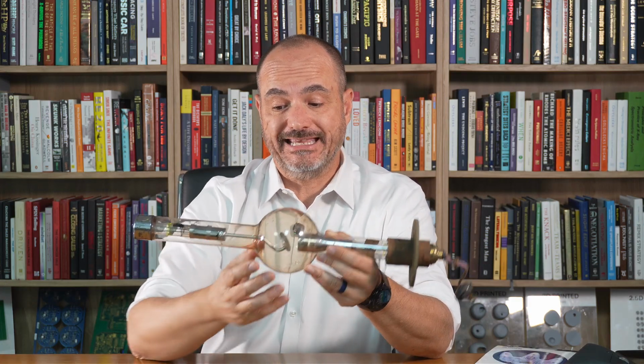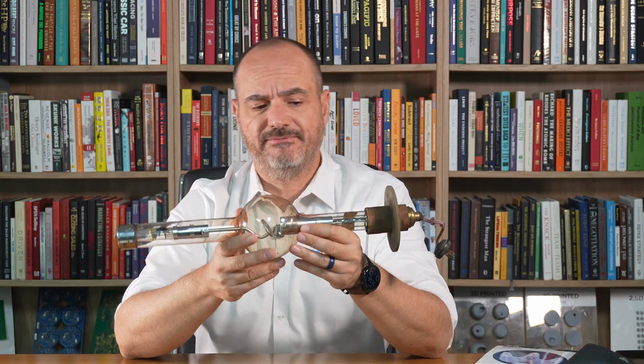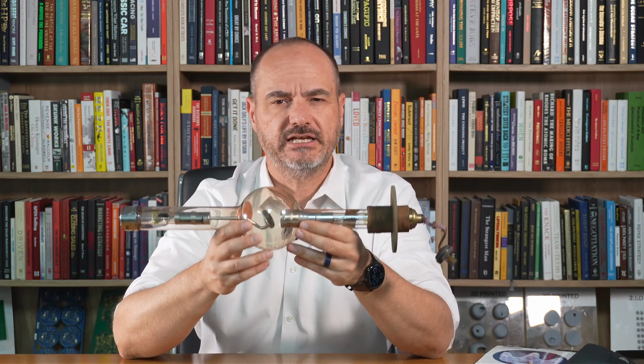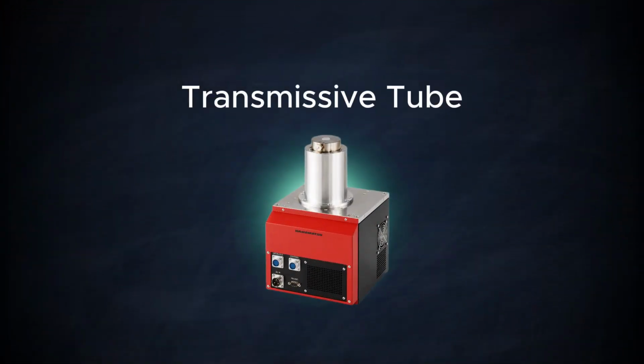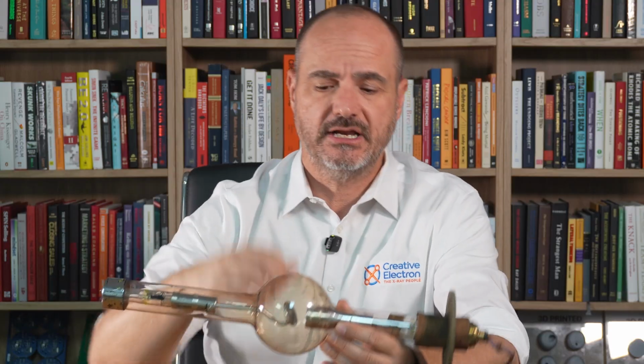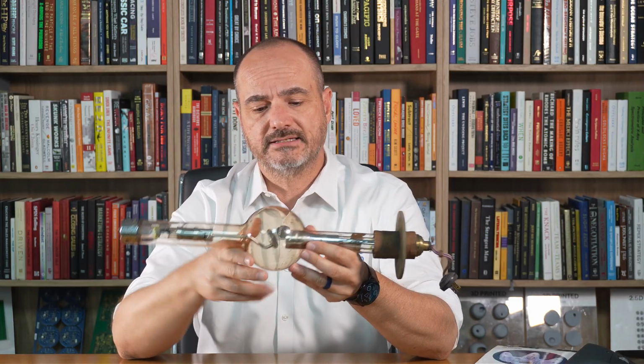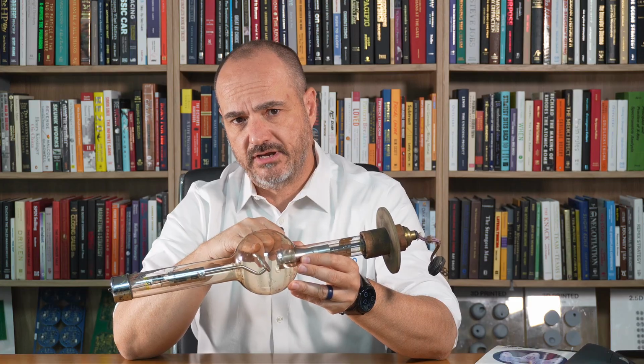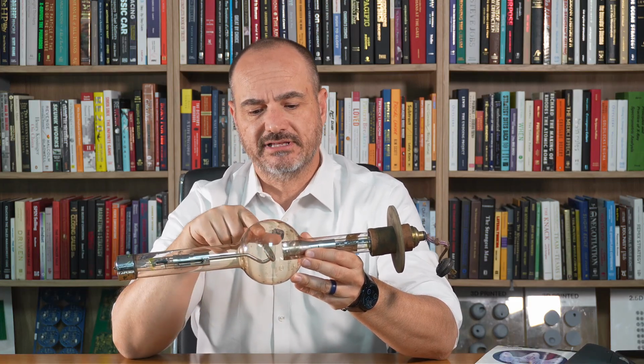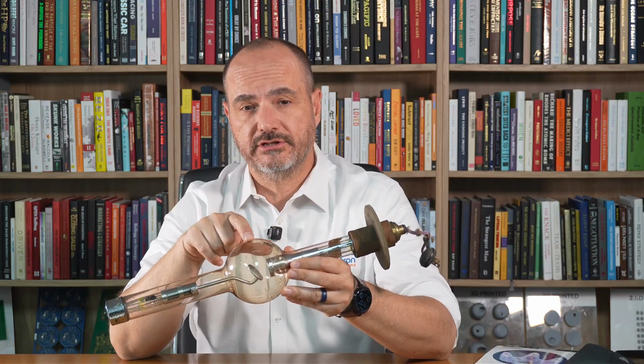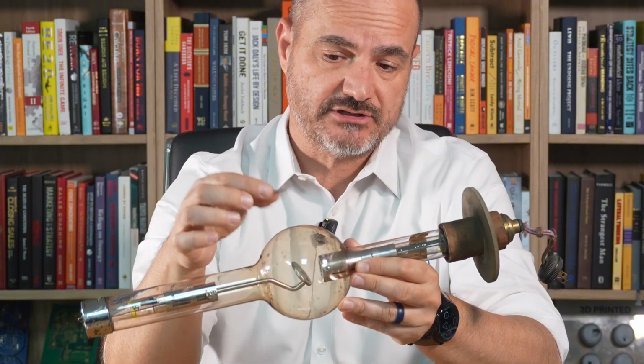Now, that's not the end of the story for closed tubes. There is a fairly new, maybe 5 to 10 year old technology in the market. It's called a transmissive tube. So it's a type of closed tube, so you don't have to replace the filament, you don't have to apply vacuum, etc. It's a closed tube, but the target, instead of reflecting, transmits. So the target is the window on the tube itself. So the target is going to be right here in the window, which allows you then to bring the sample as close as possible to the target to get the high magnification that you need for smaller components like electronics.